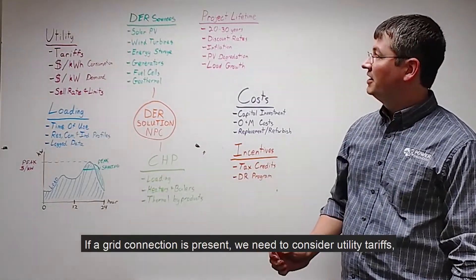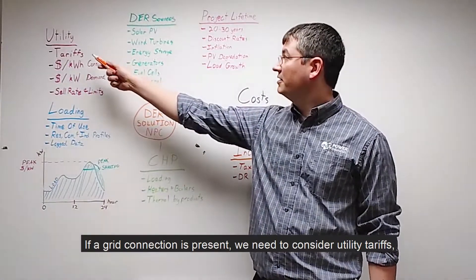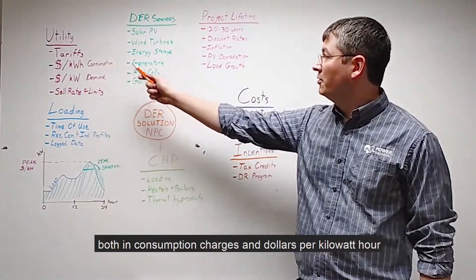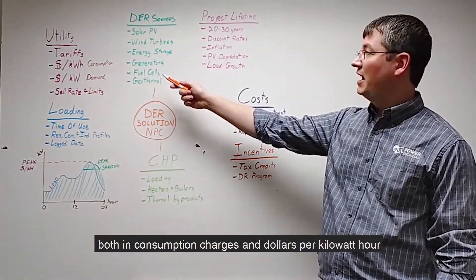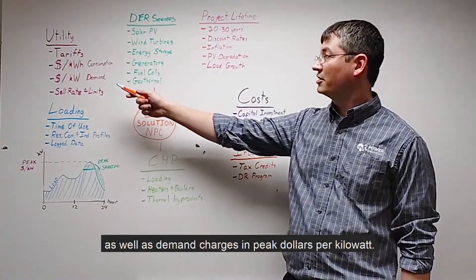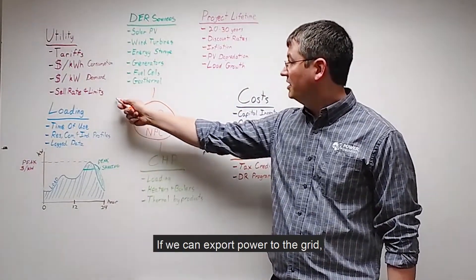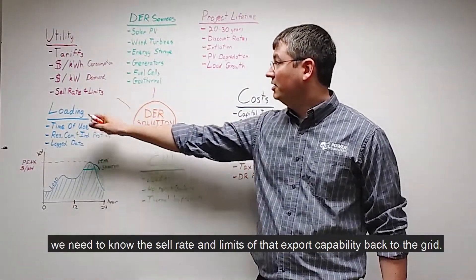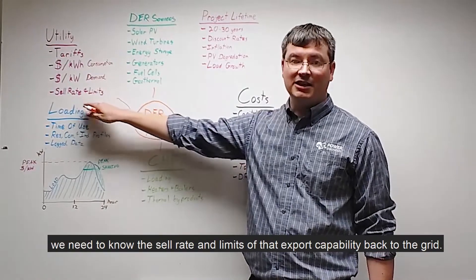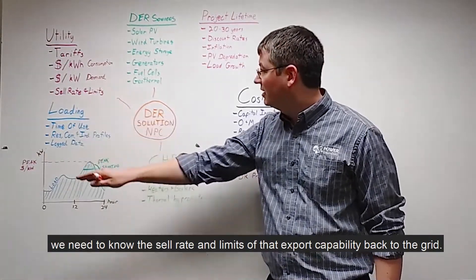If a grid connection is present, we need to consider utility tariffs — both consumption charges in dollars per kilowatt-hour as well as demand charges in peak dollars per kilowatt. If we can export power to the grid, we need to know the sell rate and limits of that export capability back to the grid.